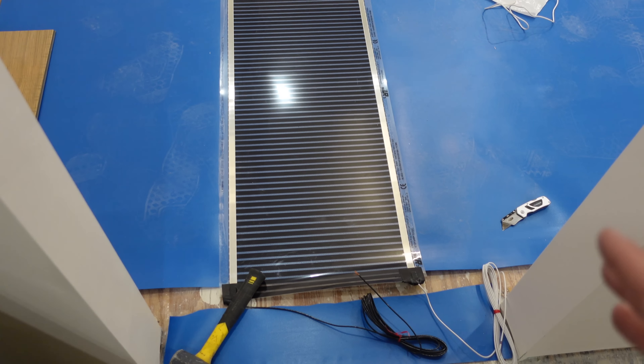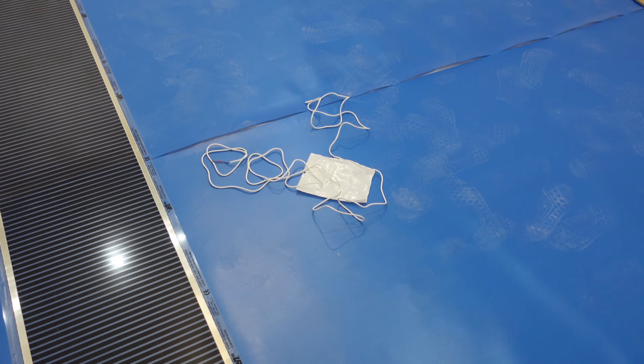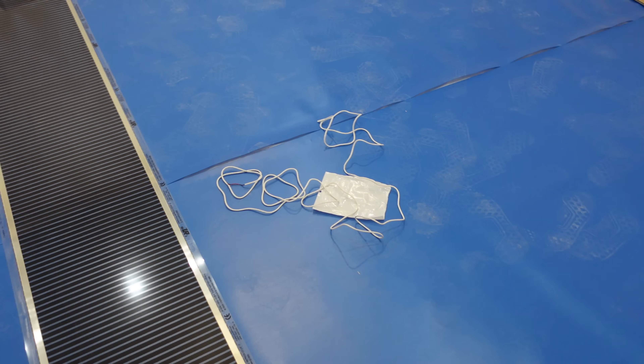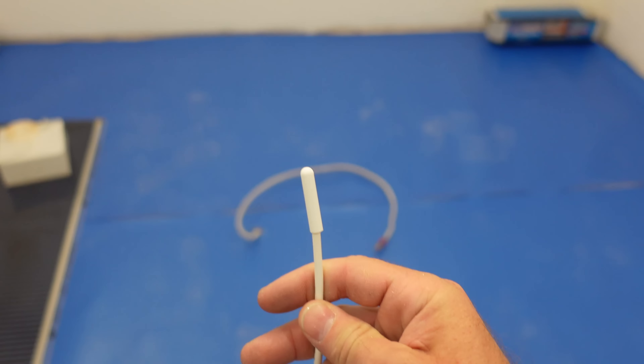We've got the first mat taped down, so it should hold itself. And while I'm here at the first mat, I'm going to install a floor temperature sensor right here. This little guy runs all the way back to the thermostat. That is how the thermostat knows what the temp in the floor is — you don't need to know the air temp, it just needs to know how warm the floor is for this to work. But they all install with that floor temp sensor.